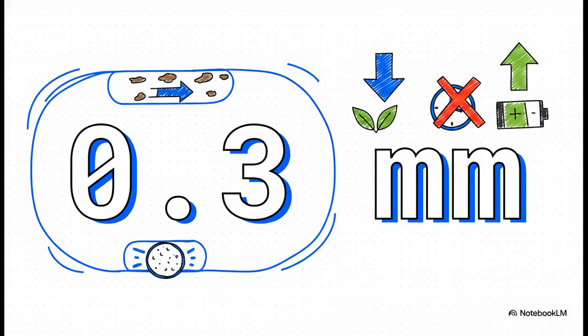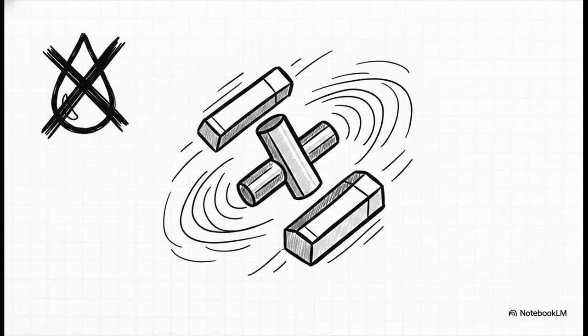So, they use ATCS, an automatic tube cleaning system. Without ever shutting the system down, it continuously shoots these special sponge balls through the pipes via water pressure, scrubbing them completely clean 24/7. Zero downtime, maximum efficiency. It's genius. Next up, the heart of the whole cooling system, the compressor. Traditional ones need oil for lubrication, but that oil eventually gunks up the heat exchangers and kills your efficiency. The fix? Magnetic bearing compressors.